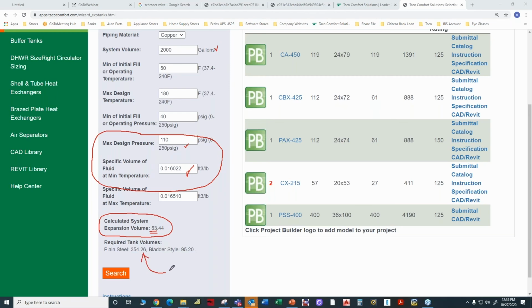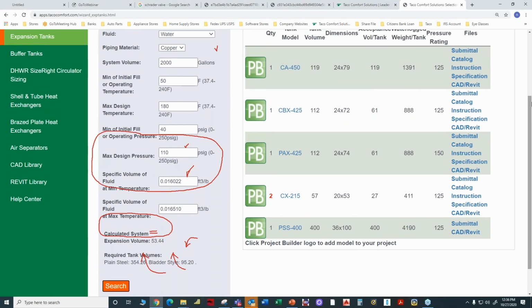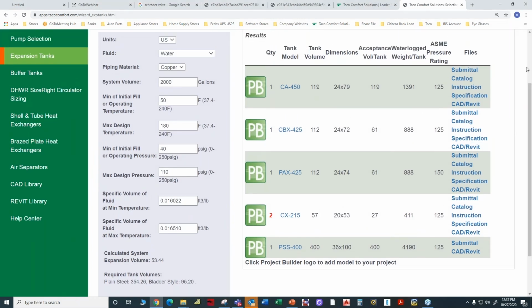We're going to skip over the plain steel tanks for a moment and focus most of our attention on the bladder style tanks. A bladder style tank would require a steel container volume of approximately 95 gallons. So let's look at what the software has selected. The software has said that, okay, in order to meet your design criteria, we're going to need an expansion tank whose steel volume container or tank container is 119 gallons. That's greater than the 95, so it meets that criteria. And in this particular case, the acceptance volume of the bladder is 119 gallons.